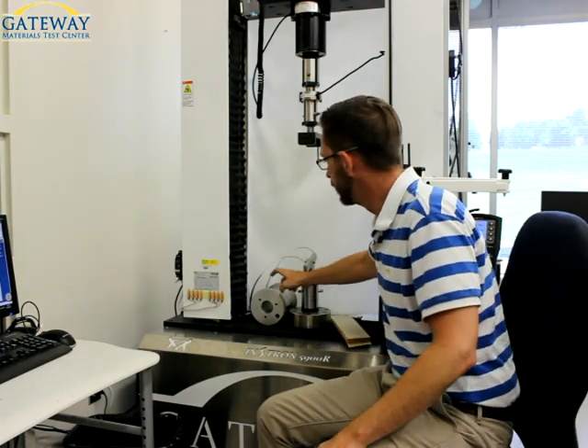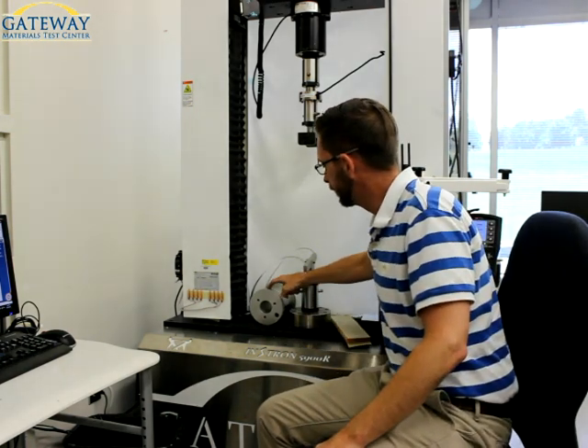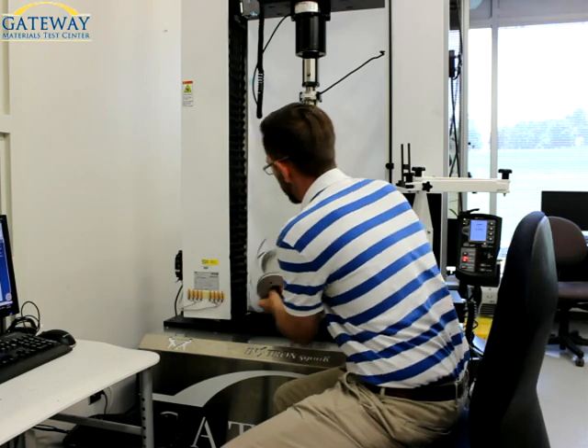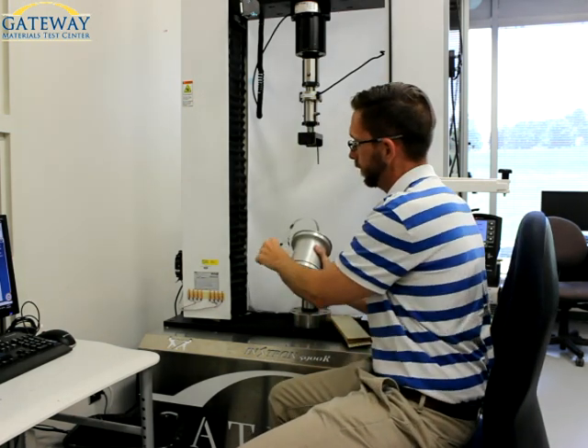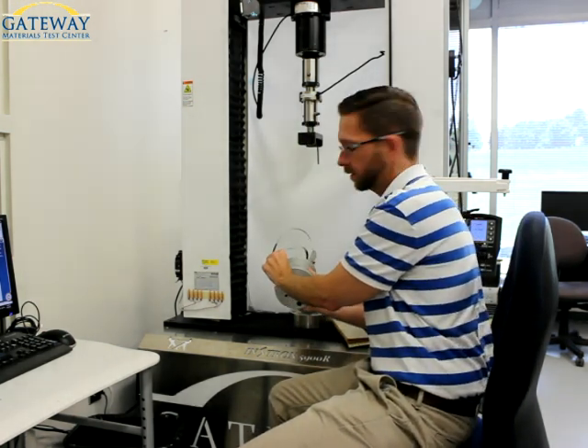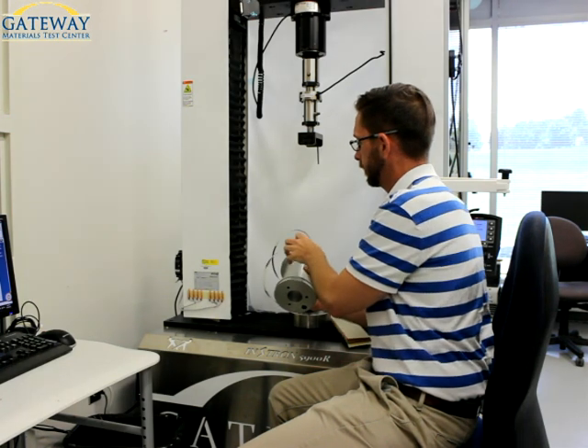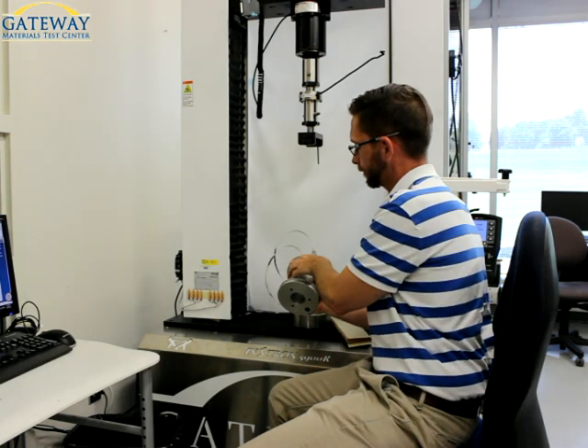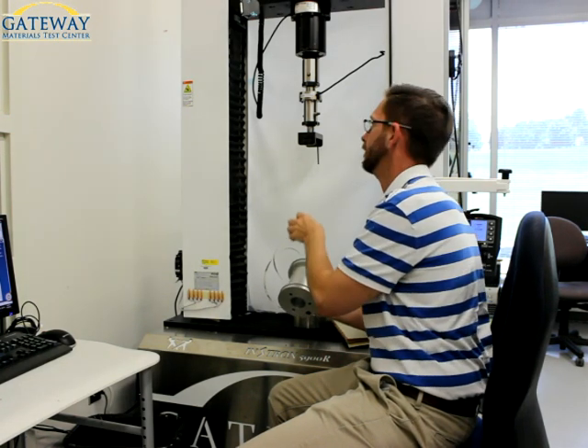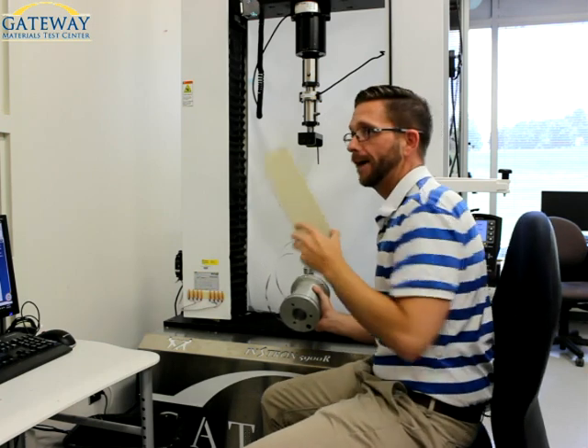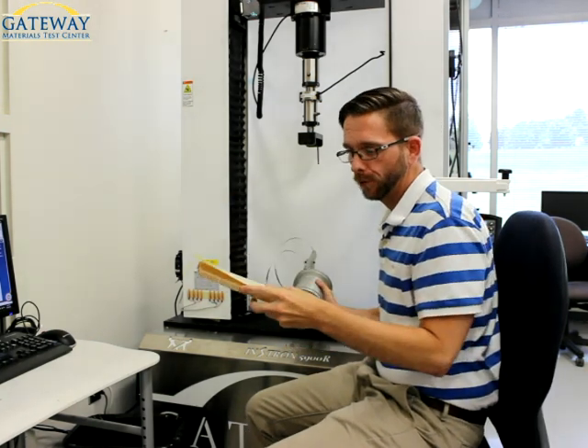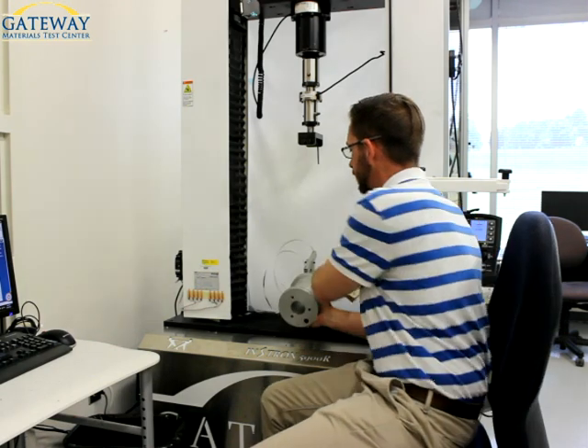So you have to have basically the outside diameter of the fixture here, plus half of these bands, minus the diameter plus half of the facing, just one facing on the specimen, and you have to subtract those two. That right there is a calibration torque value that you have to put into the method in order to get the correct torque out of the system.